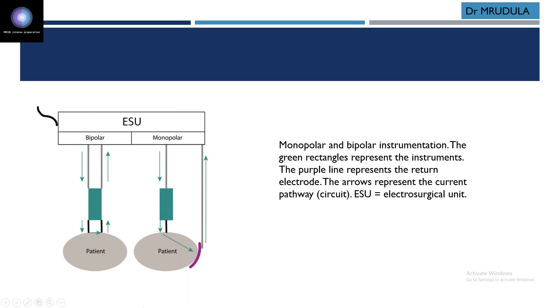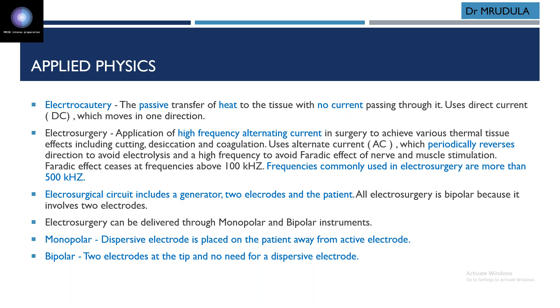While in bipolar instruments, both electrodes are present in the jaws of the instrument. There will be no return electrode. So here the chance of damage is less in bipolar instruments. Electrosurgery is always bipolar, but the instrument we are using can be either monopolar or bipolar. Monopolar means the dispersive electrode is placed on the patient away from the active electrode. What we call the cautery plate is away from the active electrode. While in bipolar, two electrodes are at the tip of the instrument and there is no need of any return or dispersive electrode.